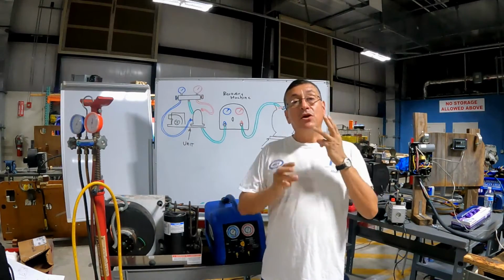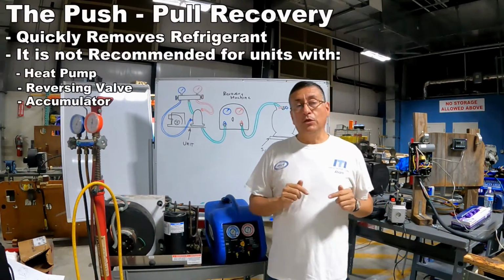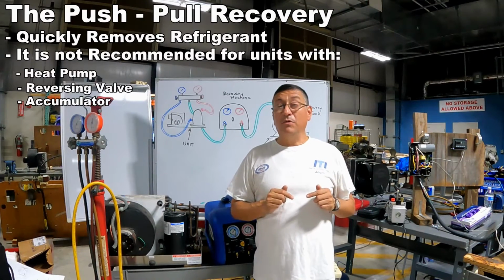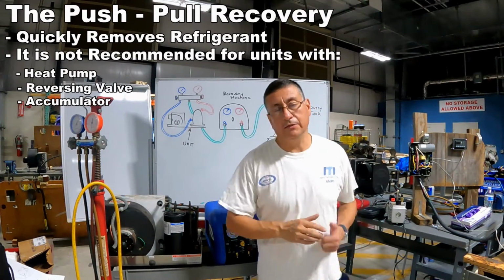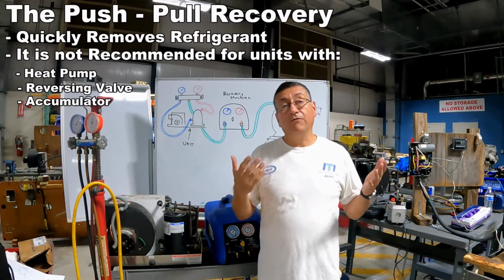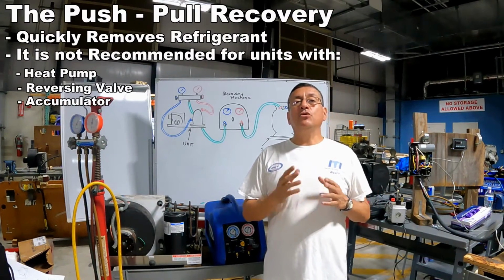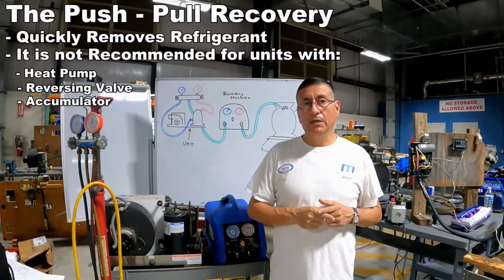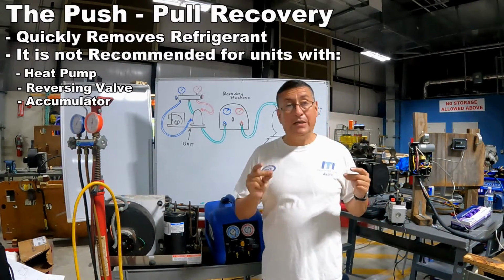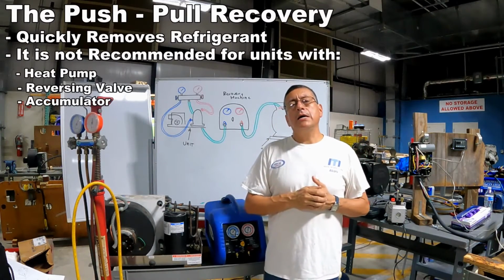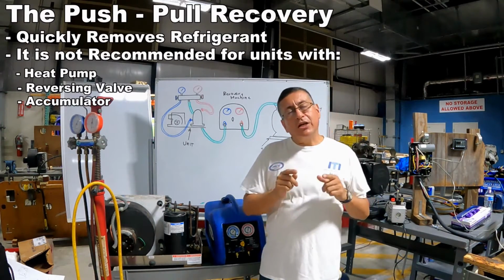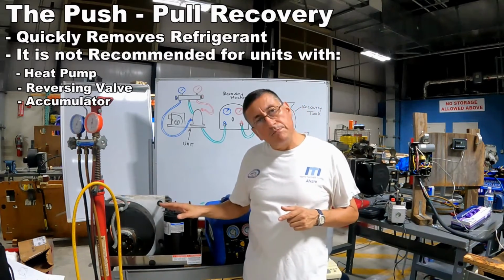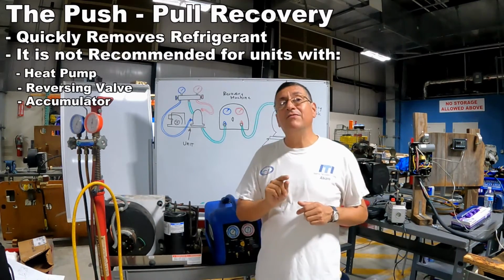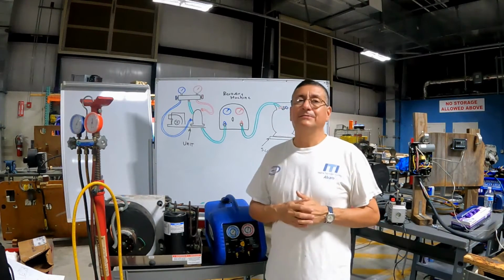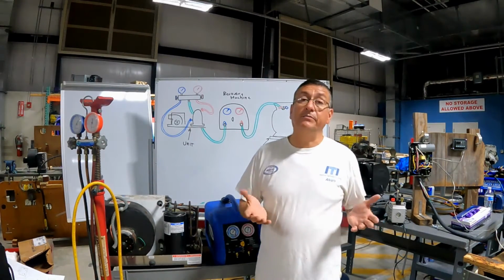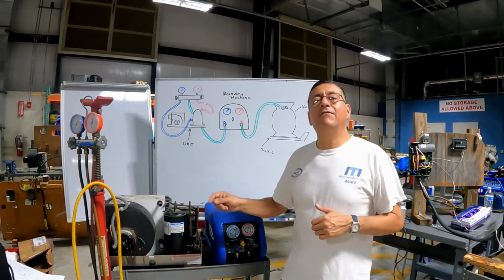And the third method is the push-pull method. This is a method for equipment with more than 10 pounds of refrigerant. Okay, it's for big equipment. And this is a method of two steps, and it is also quick. It's faster. The inconvenience: that method is not recommended if the equipment has a heat pump, or if the equipment has a reversing valve, and also if the equipment has accumulators.